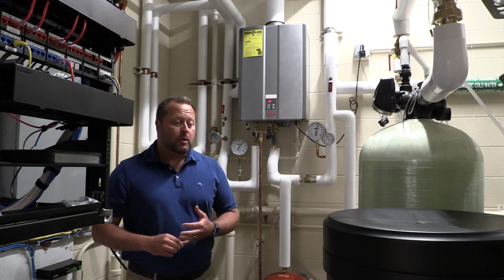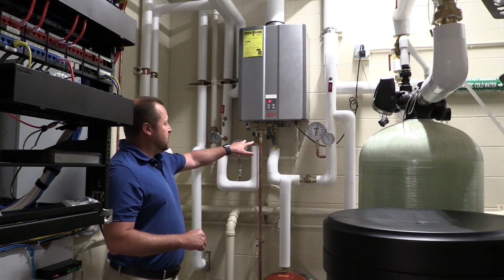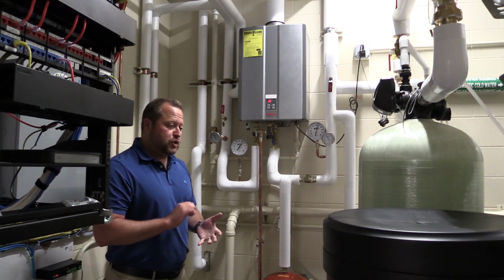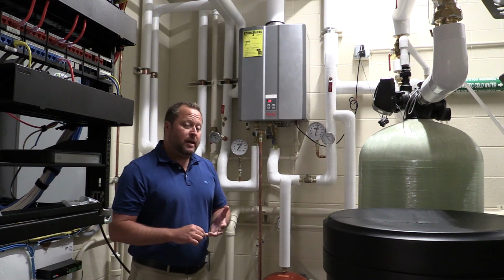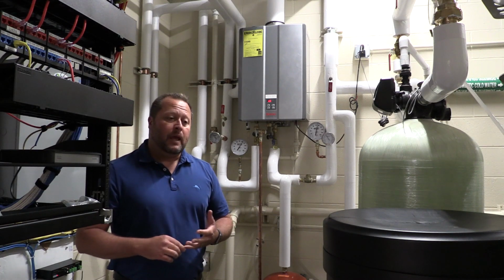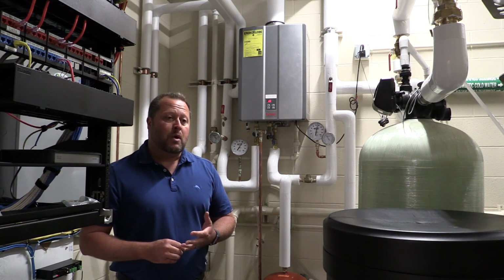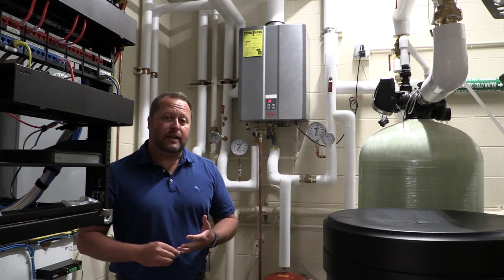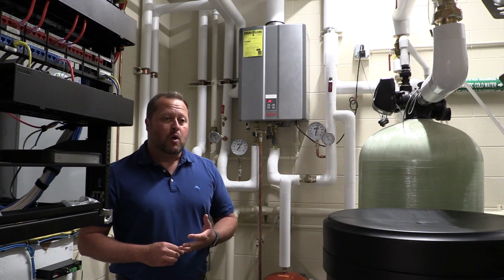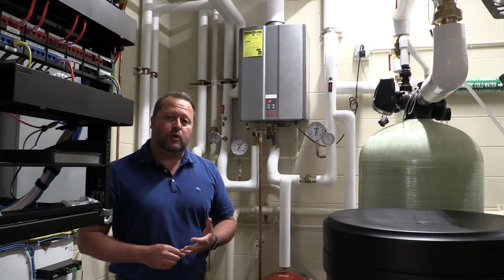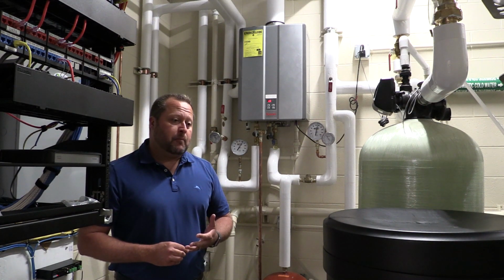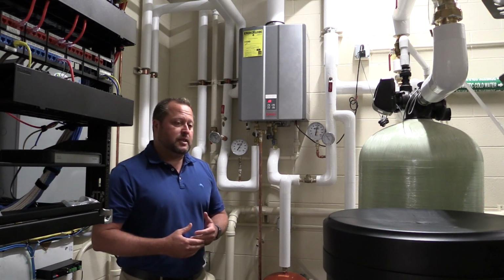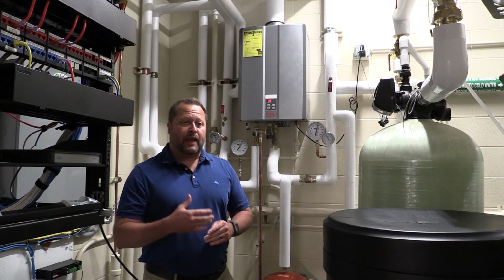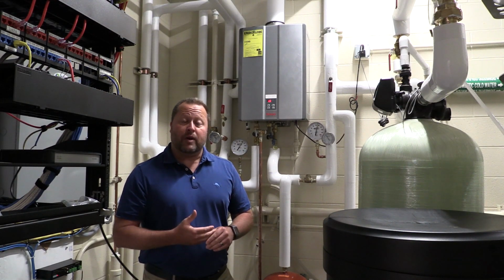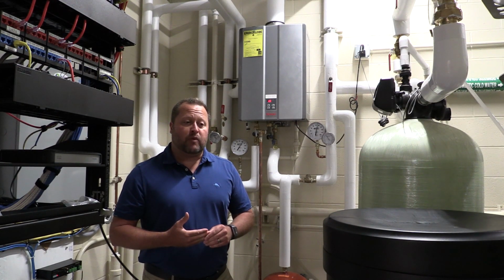So they can turn on the sink and run it 24 hours a day, 7 days a week, and not ever lose hot water. The features and benefits: isolation valves come with it. All you have to do is turn on the water. 0.4 gallons a minute is what causes the unit to fire. It has a 13-to-1 turn down ratio, so depending upon the need, it'll fire 1/13 of that 199,000 BTUs, which is roughly 15,000 BTUs, thus saving energy. That is the whole idea behind this product. It ramps up depending upon usage. So if they had multiple sinks, it could fire up all the way up to 199,000 BTUs and provide hot water indefinitely for multiple applications.